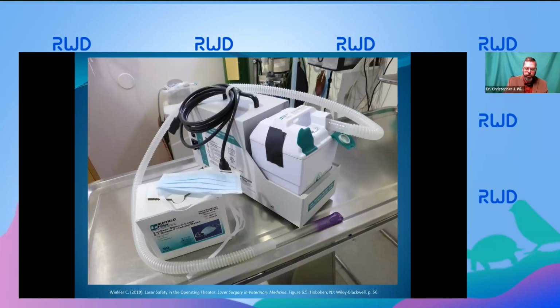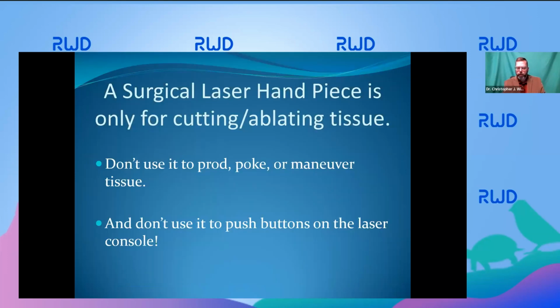Unlike diode surgical lasers, it's very important not to touch any tissue with the CO2 laser handpiece. There is an optimal focal point of distance to the tissue with these lasers, and any tissue entering the handpiece will carbonize within it. That'll decrease the beam's diameter and alter the power distribution across the beam. That can adversely affect your equipment and your patient.